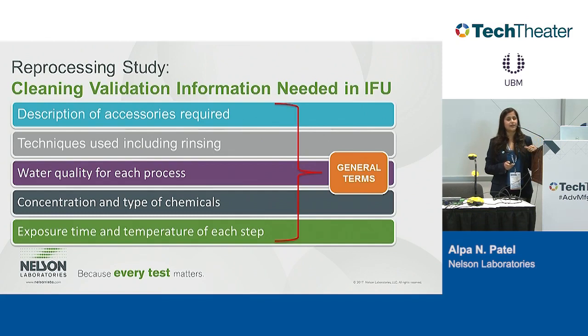our response to that was that in your IFU, do write what you want. You don't have to write everything that you have validated to, but if you put treated water, which the standards allow, because the final rinse should be performed with treated water, then it could be any water that has been treated. And if it's going through a 0.2 micron filter, it's considered treated water. So very important to know those kind of aspects: how specific do you have to be in your IFU? Because the healthcare facility will call you and say, we can't meet this because of these reasons. And he had to delay his testing, and they had to pull it out.